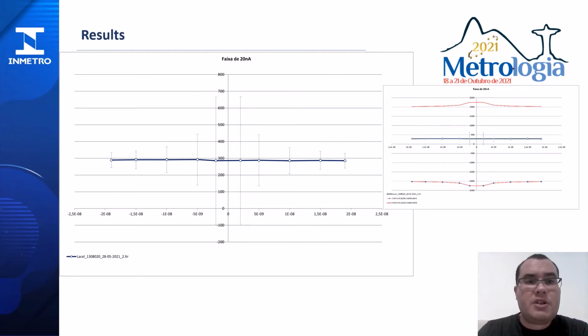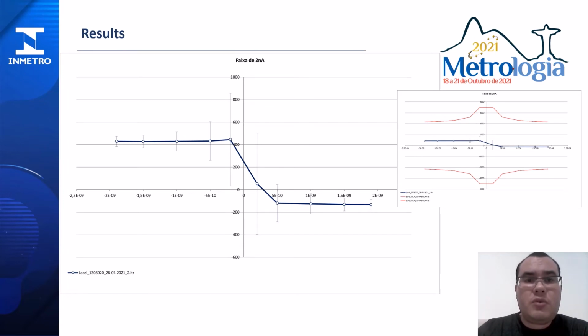This graph shows the range of 20 nanoamperes, with uncertainties also well below that specified by the manufacturer, as shown in the previous graphs. The 2 nanoampere range shows slightly different behavior from the other ranges, but still with much lower uncertainty than the manufacturer's specification. This different behavior between forward and reverse direction of the current is explained by the adjustment mode of this equipment, which has a separate adjustment for the positive part of the range and the negative part of the range.